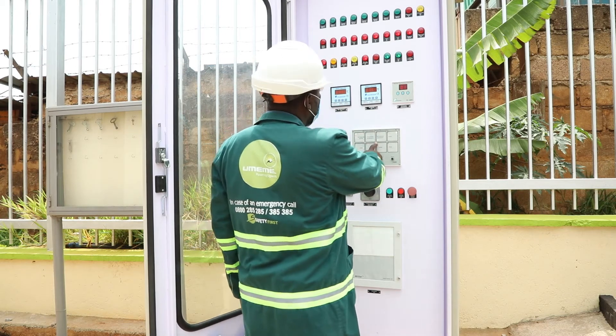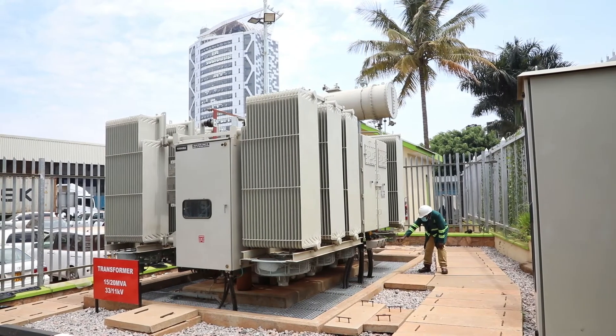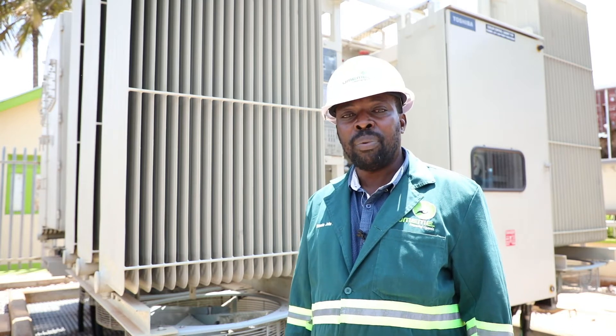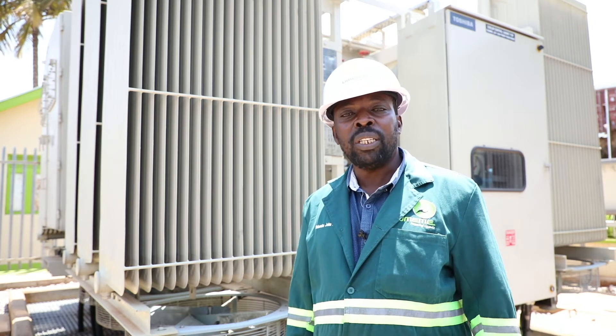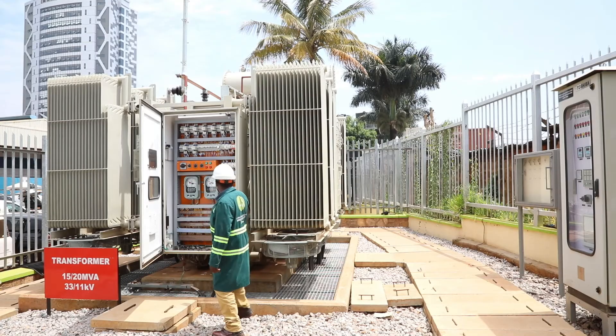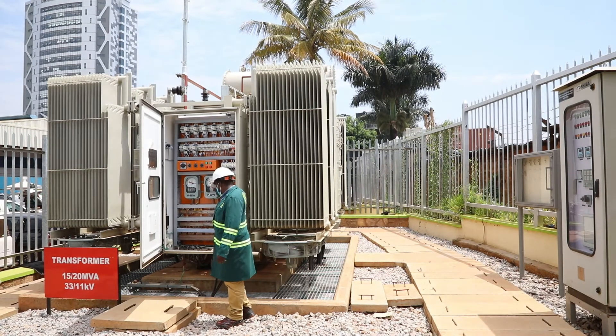When you look at what we have now and the developments in the area — we have that URI building which was not there before, and right now it's taking two megawatts. When you look at the line which supplies Mbuya, it has 2.5 megawatts. When you look at SPIA — that line which we call SPIA — supplying the industrial area of Mukwano, Pepsi-Cola, all those industries — it has gone up to 4.2. When you compare the Rogogo line which was supplying the entire area of Nakawa as only one line, it could not take all that load. So there was a need to put a substation in this area to support the growth of the area.